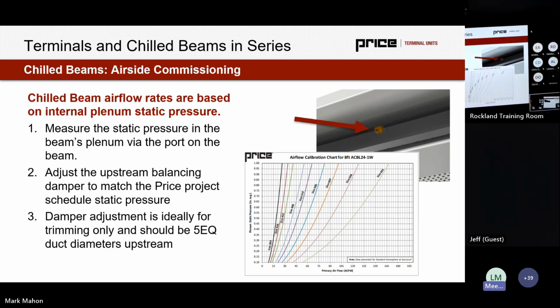Similar with a beam as we look at with a square plaque diffuser, you can get to a point where you dump and it's not effectively mixing in the space, and we're not getting induction in the case of a beam, or we're not getting proper mixing out of a square plaque diffuser. It's the same scope and discussion, whether we're using air outlets as an endpoint or we're using beams. We need to be cognizant of what the turn down capabilities are of the product. And sometimes that can be application specific or product specific.